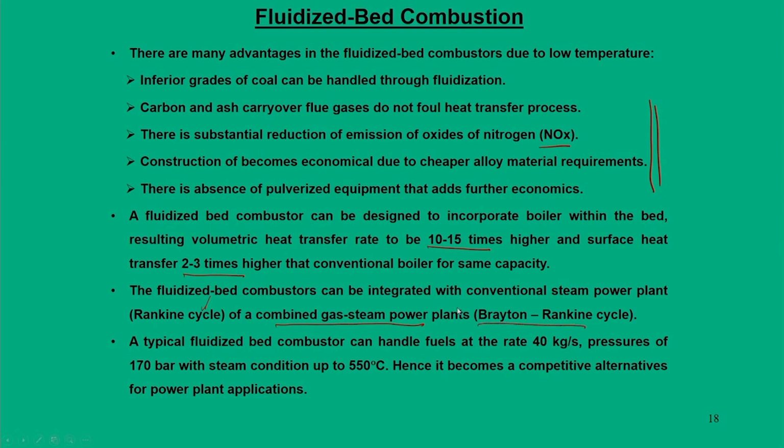And more specifically, it also caters to the needs of steam power systems which work up to 170 bar and 550 degrees centigrade, and it can handle a fuel flow rate of 40 kg per second. Hence, the fluidized bed technology becomes an attractive alternative for power plant applications. So, this is about fluidized bed combustion.